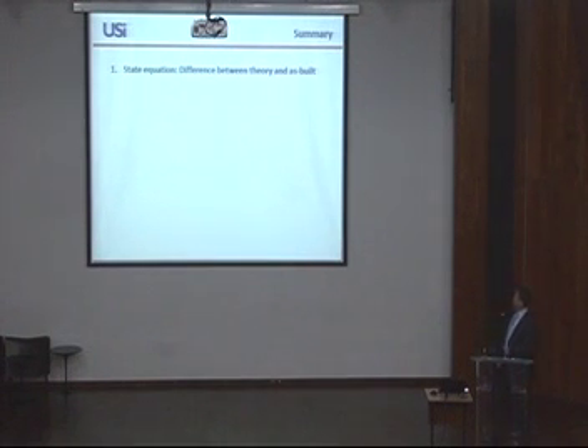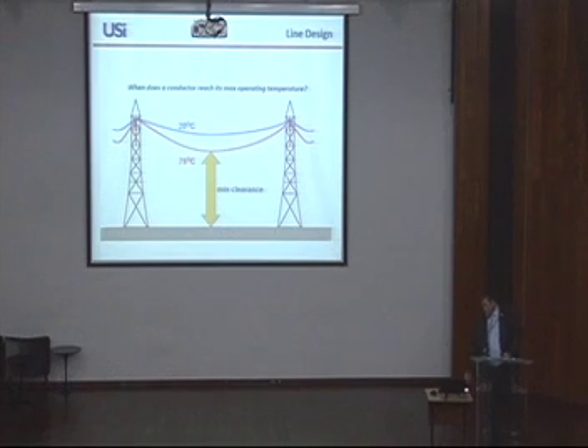Okay, first summary, state equation: there is a difference between theory and as built in the line. Coming back to the same picture as the beginning. So now, when does the conductor reach this 75 degrees? How do we know? Theoretically, we know when we have 75 degrees, we have reached the minimum clearance. But how do we know what the conductor temperature is?